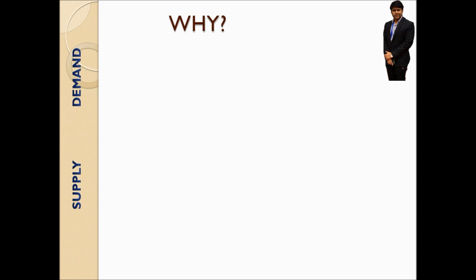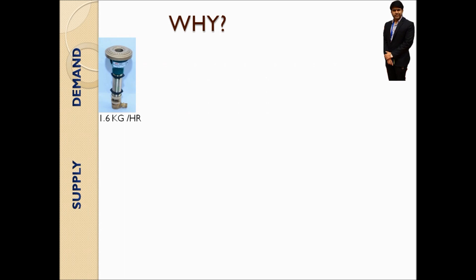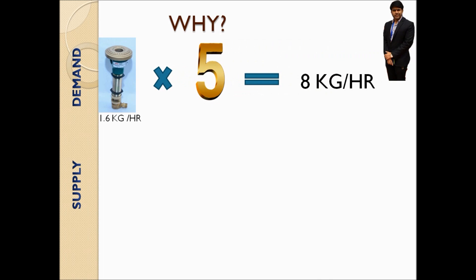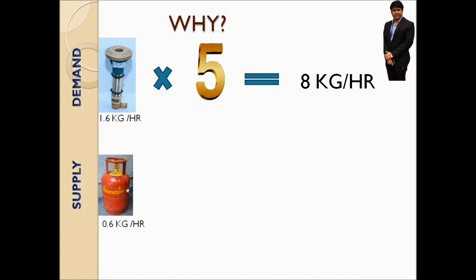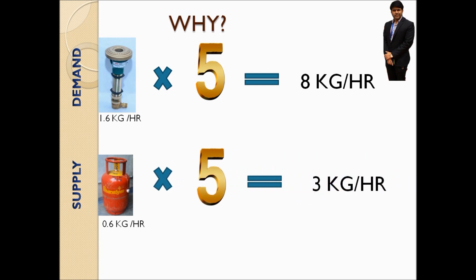I will explain this phenomenon with the help of an illustration. Assume there is a restaurant using a CD5 burner with a consumption of 1.6 kg per hour. If you use 5 such burners, the total consumption would be 8 kg per hour. Now, the vapor rate of a cylinder is 600 grams per hour, and if a gas mechanic has installed 5 such cylinders, the supply of gas will be 3 kg per hour.